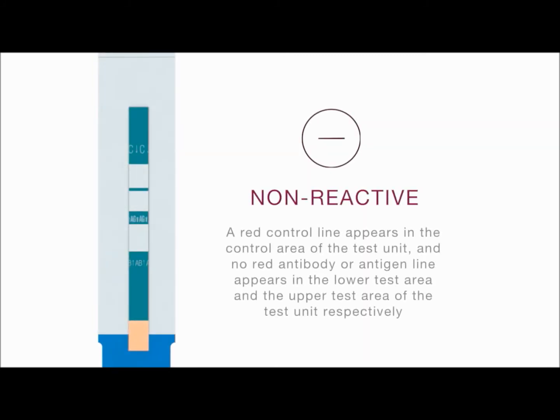Non-reactive: a red control line appears in the control area of the test unit. No red antibody or antigen line appears in the lower test area and the upper test area of the test unit, respectively. A non-reactive test result means that HIV-1 or HIV-2 antibodies and HIV-1 P24 antigen were not detected in the specimen.